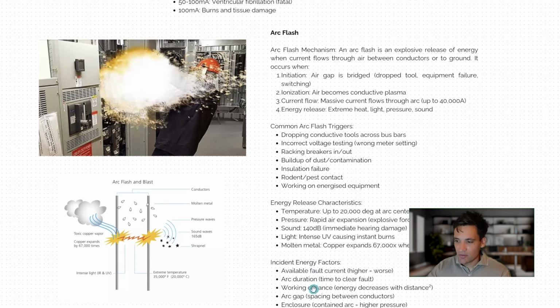The severity of an arc flash event is completely dependent on the available fault current. That's why you won't get huge arc flash events in your house, because there's just not enough power going to your house.